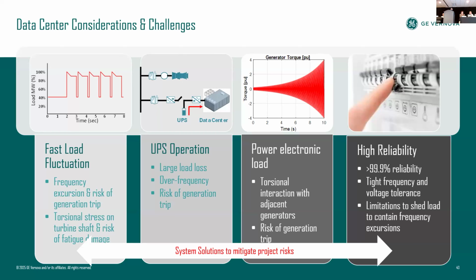So when we talk about some of the challenges with the data center, the first one is obvious. We all know that when the data center is in the training phase, it has a profile where the amplitude varies significantly, and it will be continuously pulsating at a certain frequency, right? Normally, we have seen a 1 Hertz pulsation where the amplitude can vary anywhere from 60% of the rated load up to 100% in a matter of cycles, right? So we're talking about the load pulsing in a matter of cycles.